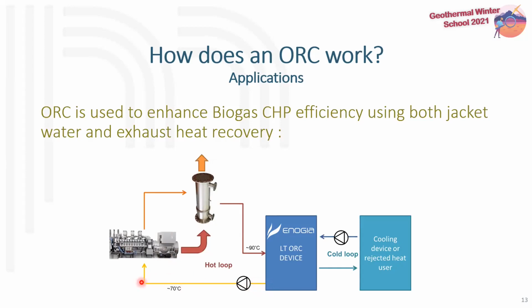We'll go to the water jacket of the genset to cool it down, and after that we'll go through a heat exchanger, a tubular heat exchanger, with the hot part being the exhaust gas and the circulation of water, and we will get around 90 degrees for the hot loop.